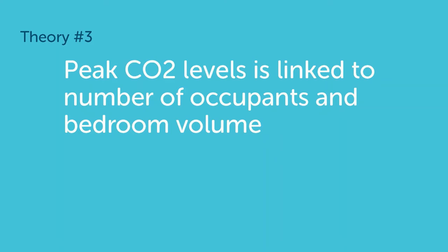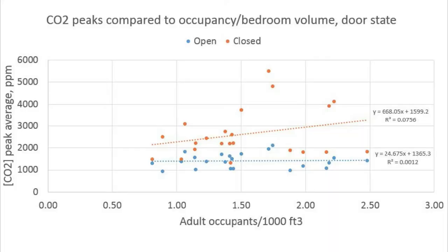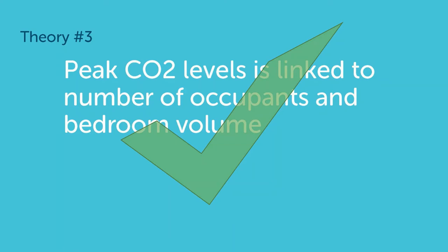Theory number three: peak CO2 levels are linked to the number of occupants and bedroom volume. In other words, the more people and pets and the smaller the room, the worse the CO2 will be. This graph shows the occupancy of each bedroom per 1,000 cubic feet when the door was open and closed, and the corresponding peak average of carbon dioxide in the room. You can see that the CO2 somewhat corresponds with the number of people per volume, but not as closely as you might think. And what would you do about this anyway? Kick people out of the bedroom? Good luck explaining that one to the toddler in the room.